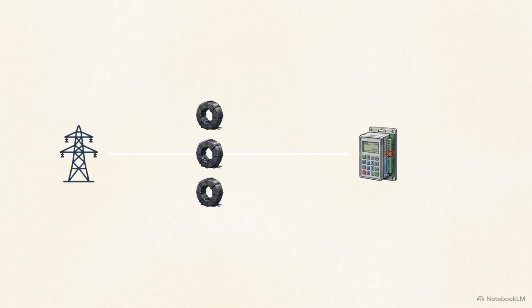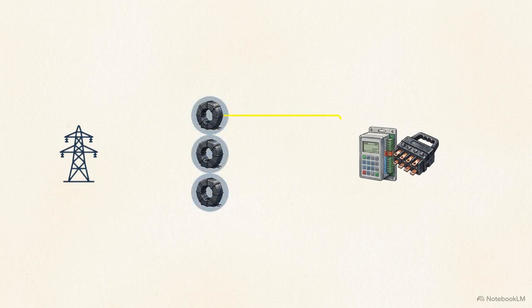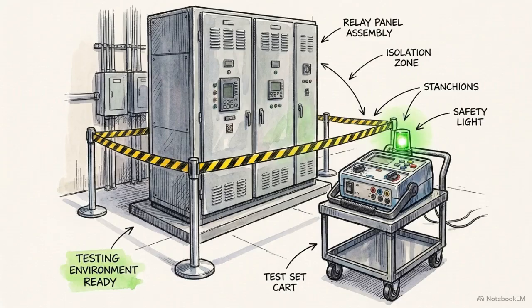Mechanical isolation follows. Technicians insert highly engineered test plugs directly into the relay to sever the connection to the external grid. This action simultaneously shorts all unused current transformer, or CT, circuits. Because an open CT circuit on a live system generates lethal secondary voltages, this physical shorting is a non-negotiable safety mechanism. Only after locking down the physical boundary and isolating the workspace from the analog grid is the environment considered ready for secondary current injection.